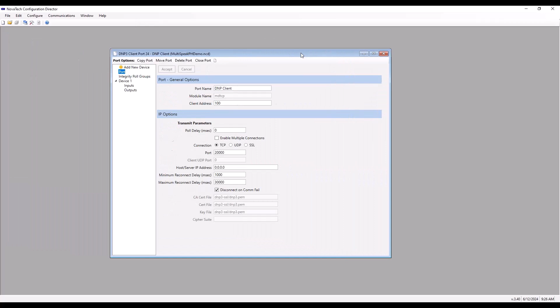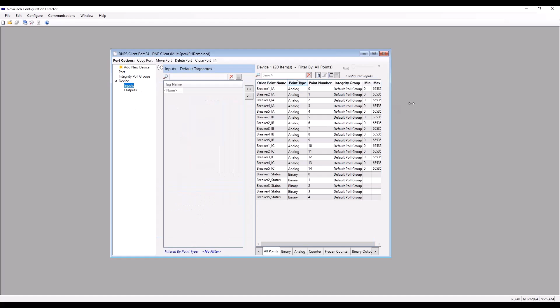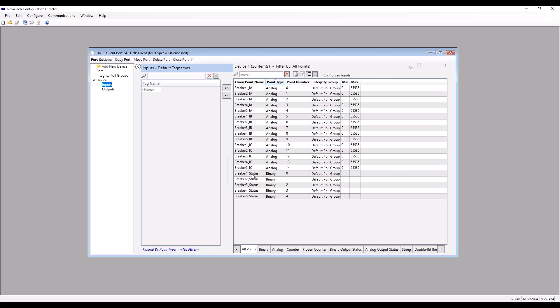I've done a bit of legwork on this NCD file already. I configured one DNP client port on this manufacturer-agnostic device, creating simple binary and analog inputs. Note we've got breakers 1 through 5 status points and 3-phase currents for all those breakers — these are the points Brad will use in his MultiSpeak demonstration, so keep in mind we've got 5 breakers mapped over this multi-speak port.